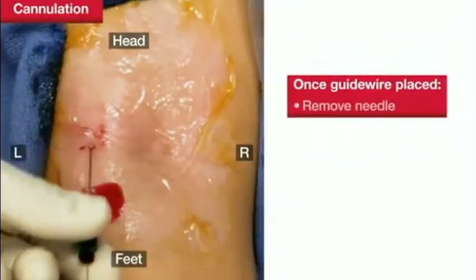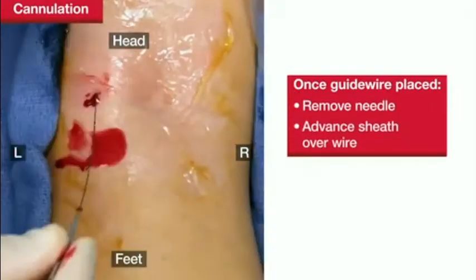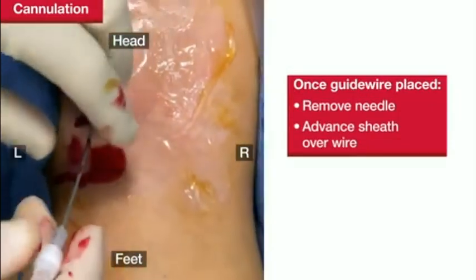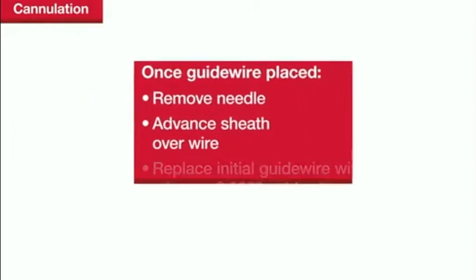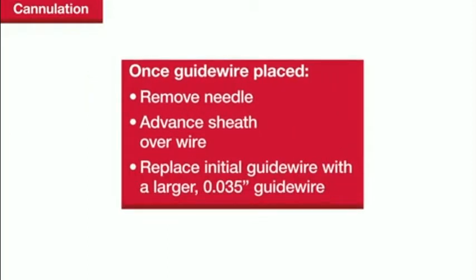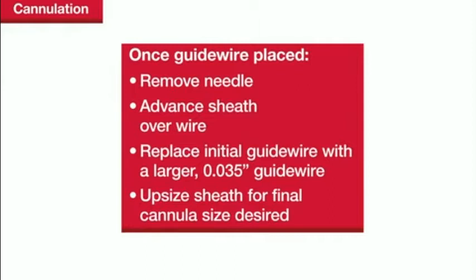Once the guide wire is in place, remove the needle and advance the corresponding micropuncture sheath over the wire. A 4 French micropuncture sheath accepts an 0.035-inch guide wire, and the sheath can be upsized over this larger wire for the final cannula size desired.